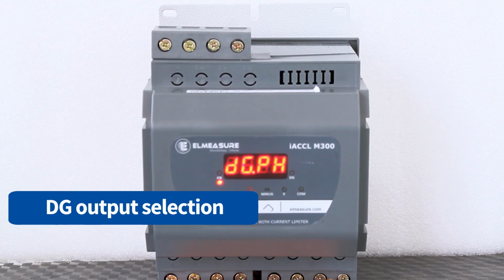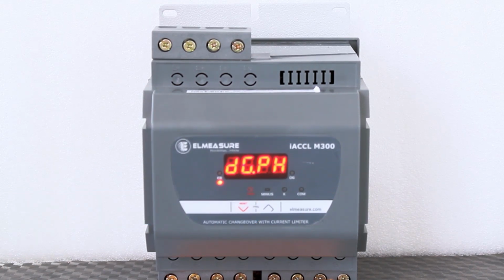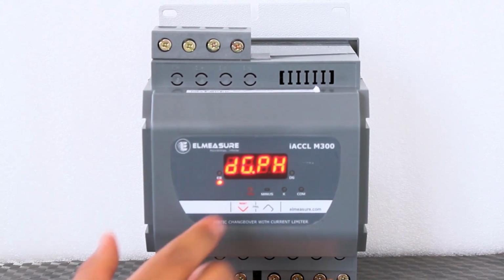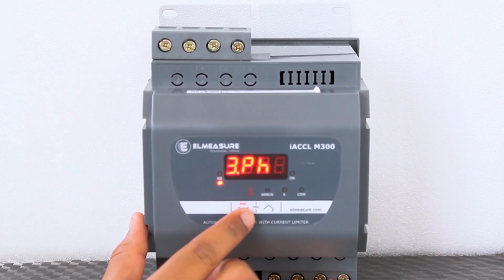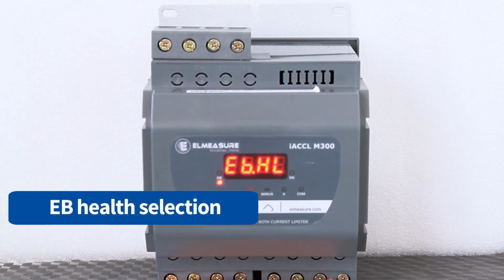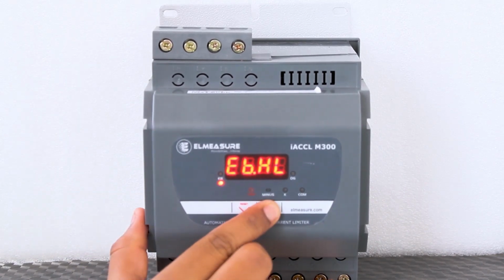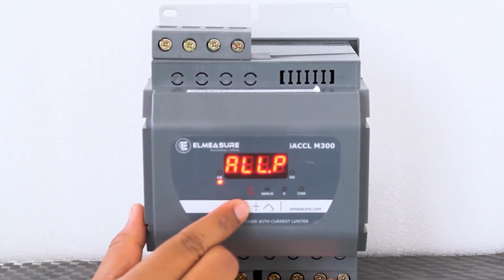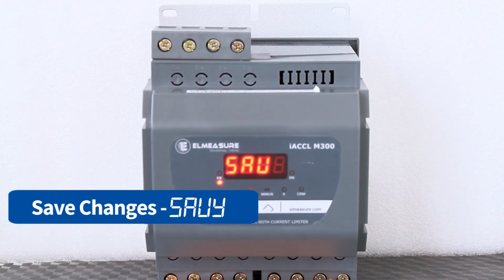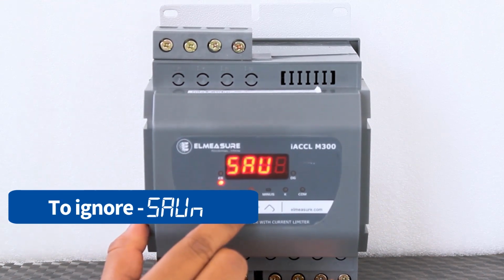This is DG output selection. By default it will be 3 phase. But you can program it for single phase also. This is EB healthy selection. Here you can see the status for all phases. If you want to save the changes, press Y. To ignore the changes, press N.